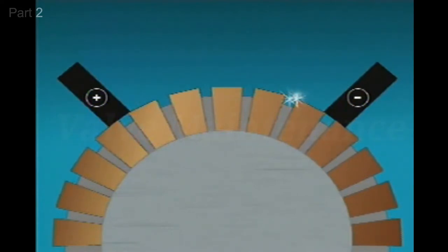The sparking may be minor, or it may be extreme, causing what looks like a ring of fire around the commutator. Sparking always indicates a problem in motor operation.